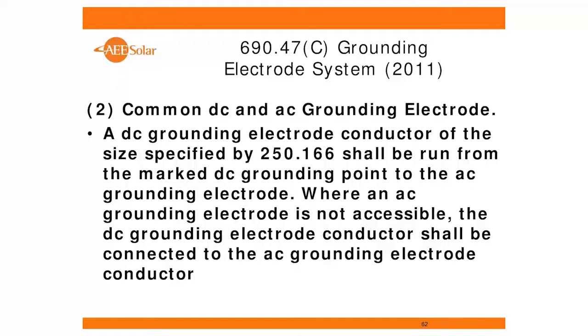Number two is really the same as number one, except you're going to the same electrode. So let's say you have a driven ground rod or whatever it is, then you're going to take your grounding electrode conductor over to that driven ground rod, which is where the grounding electrode conductor from the AC service is also tied into. That's fine too.